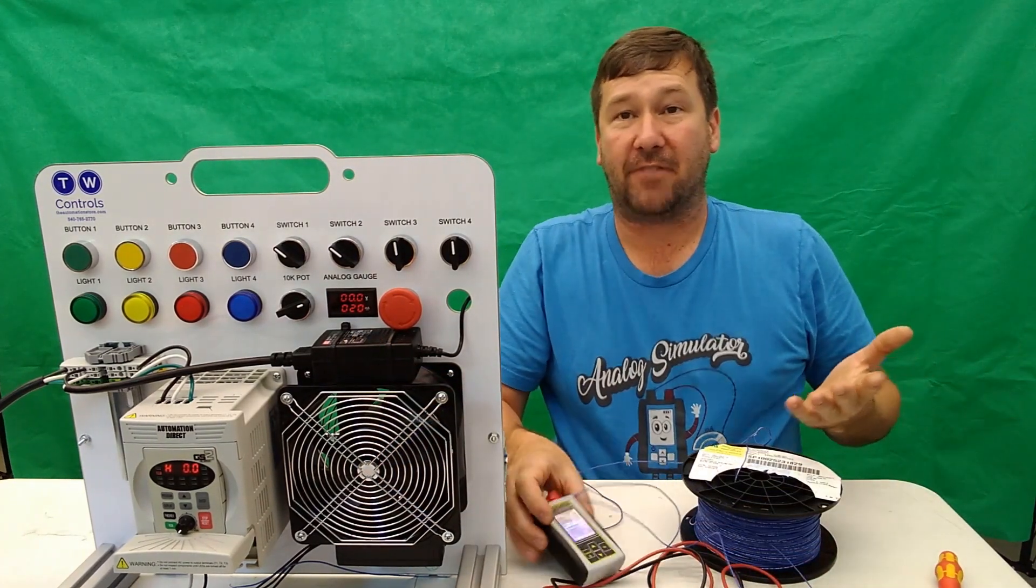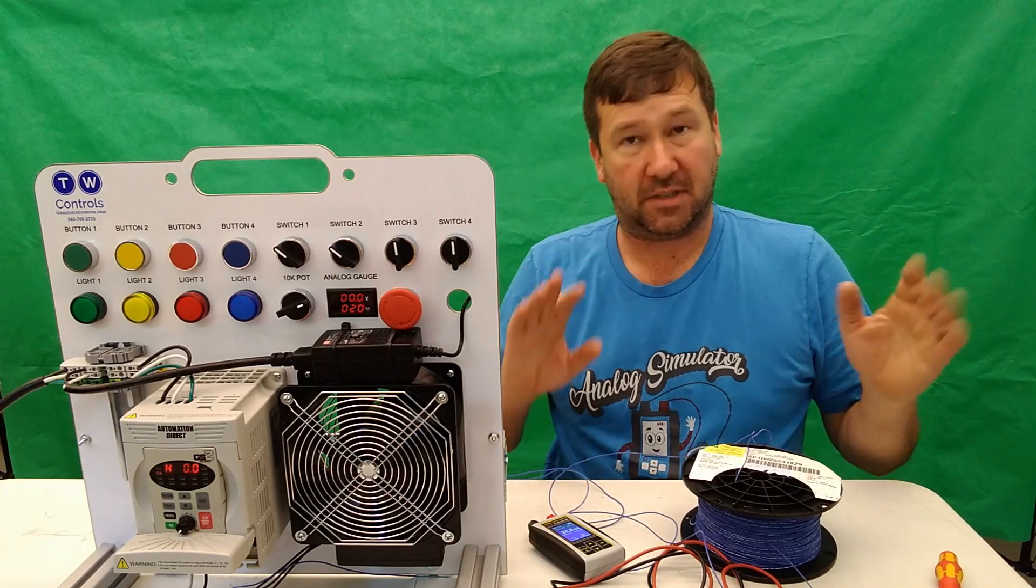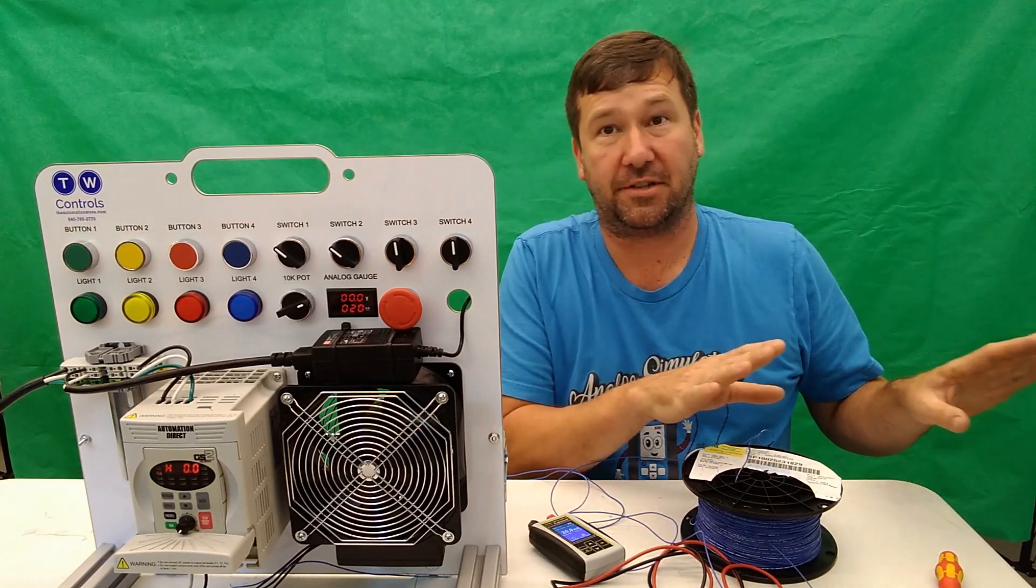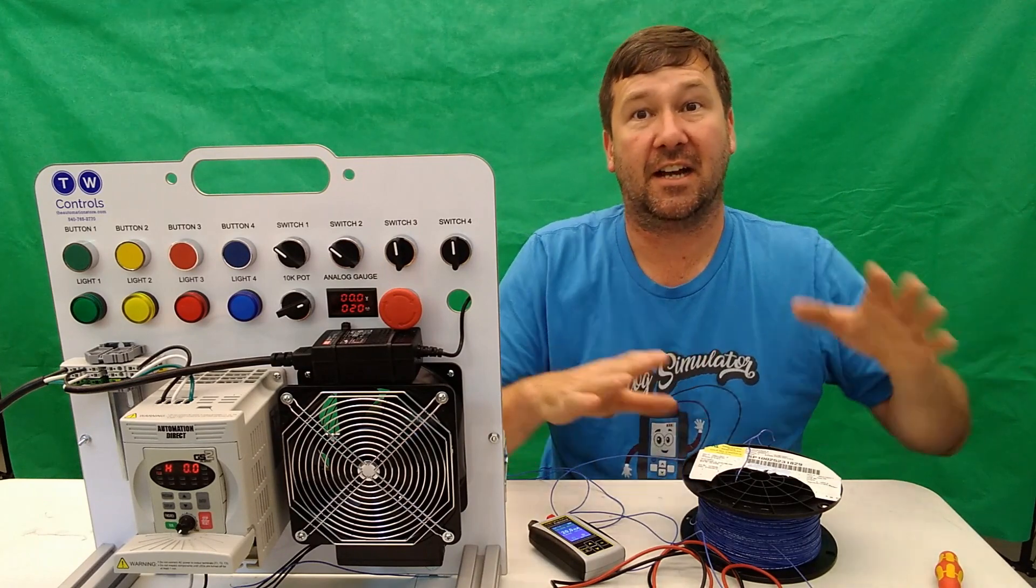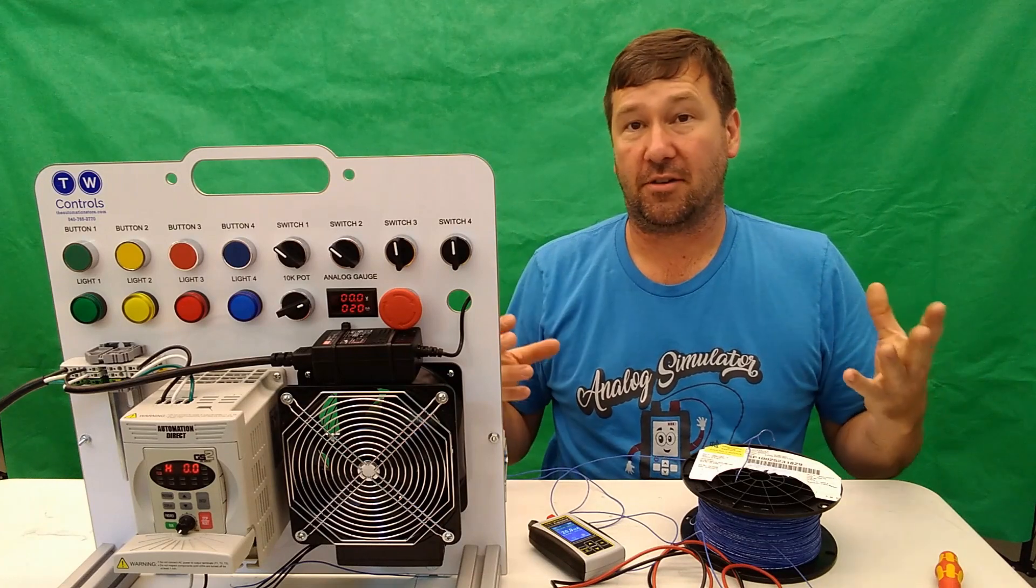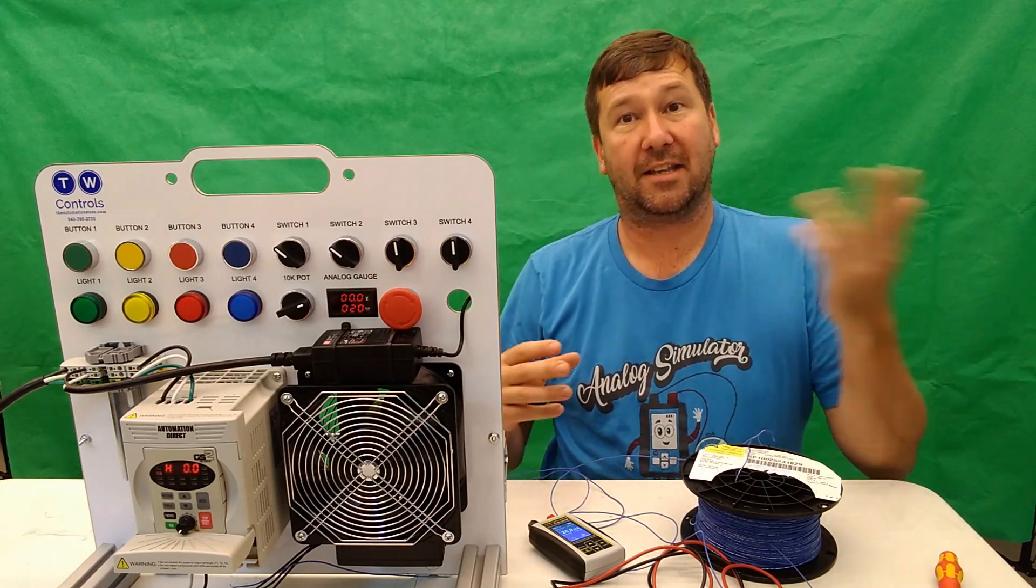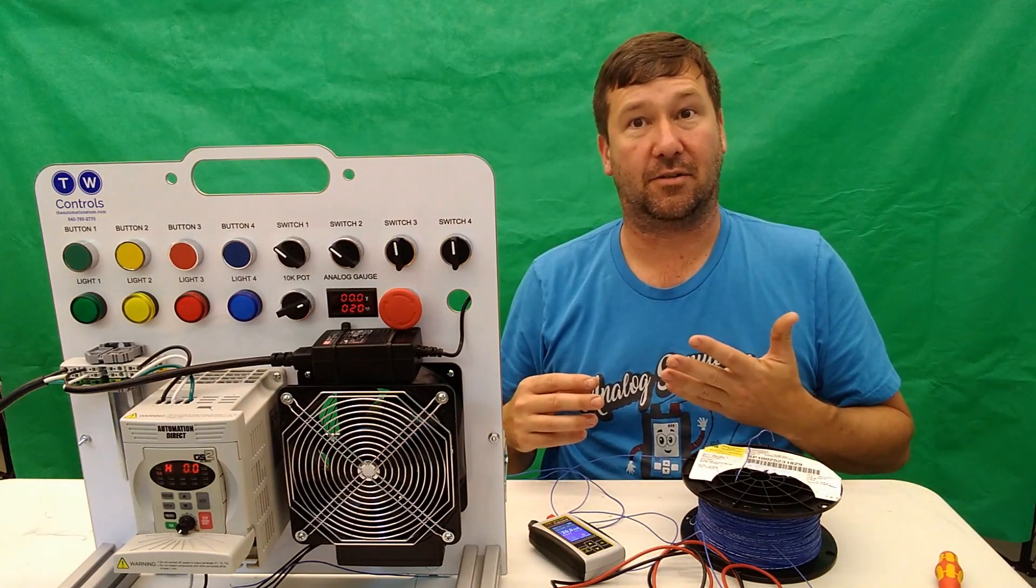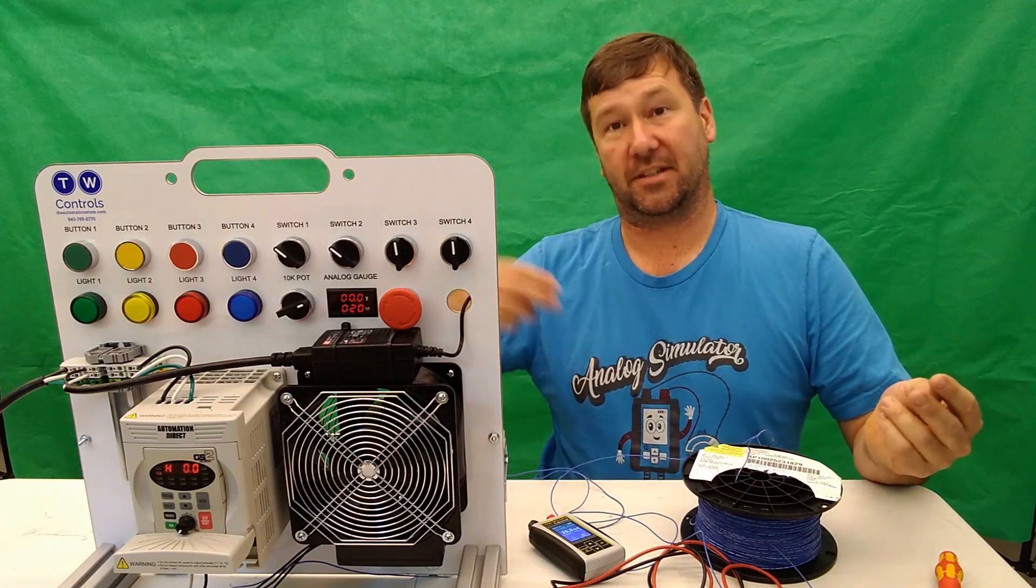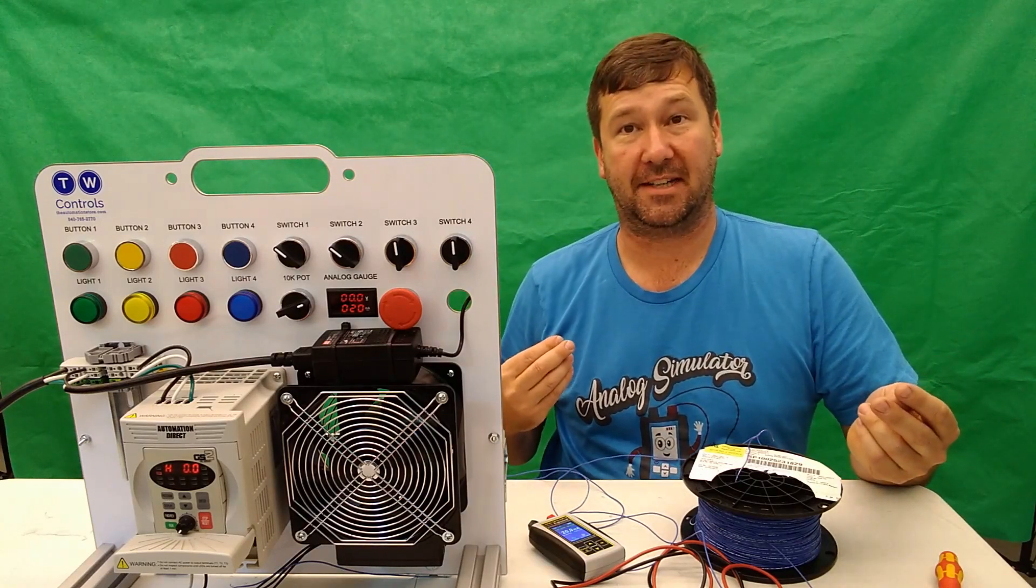And that's the advantage of a milliamp signal. With the exception of leakage current and things that we'll address in the troubleshooting section of this series, milliamps in equals milliamps out. So as long as your load is not too high that it can't drive the signal, you'll have the same signal at your instrument that you're going to have at your PLC input.